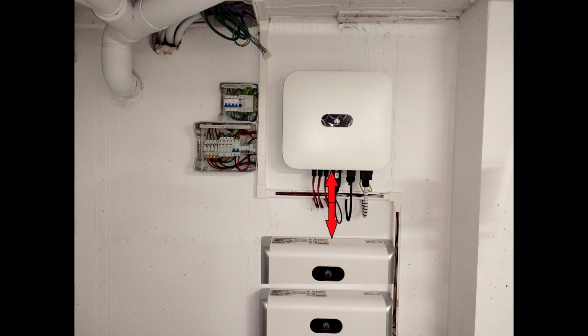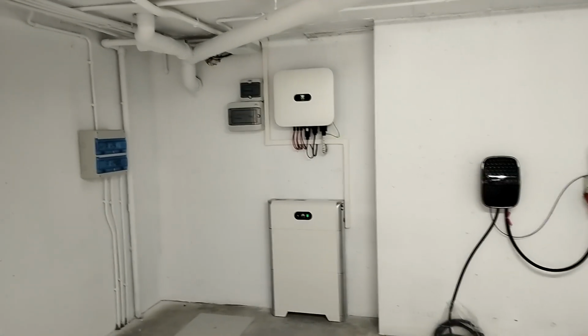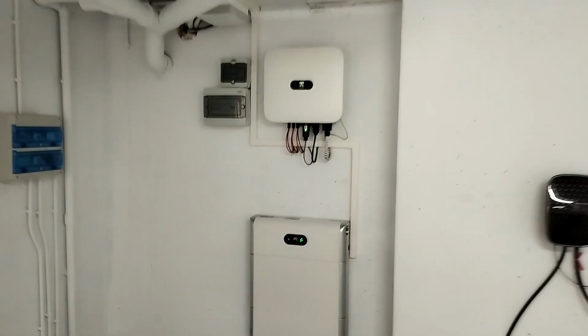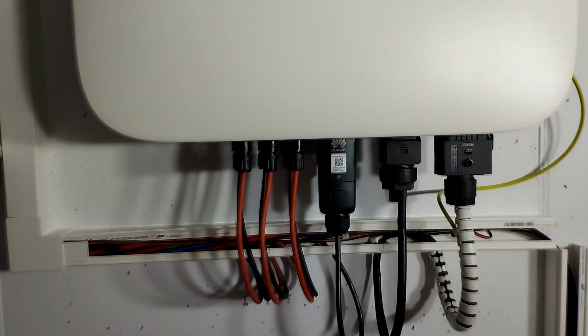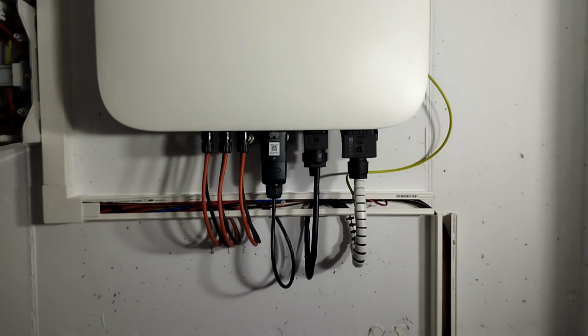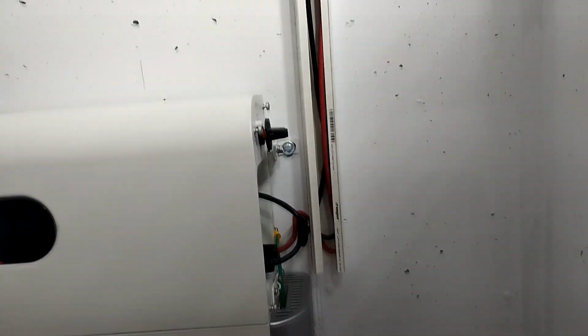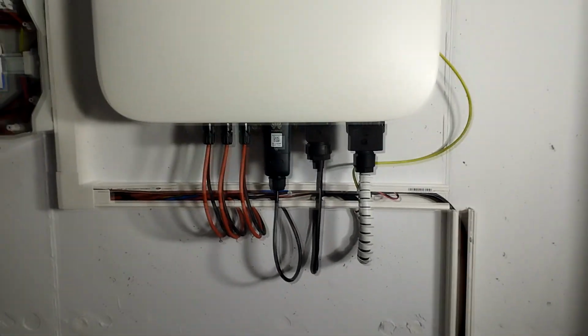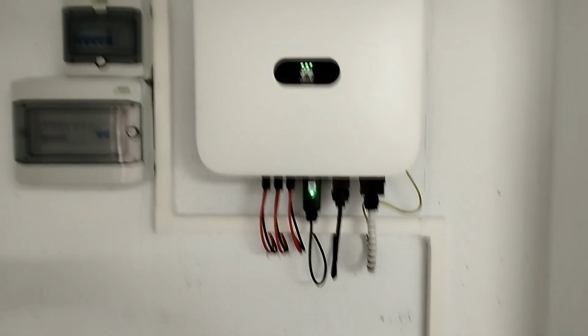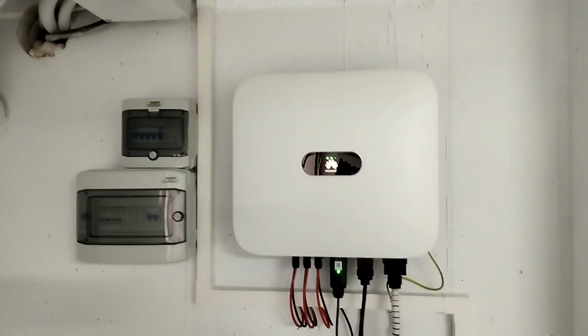Naturally, both the inverter and the battery are heavy, especially the battery, and must be securely mounted to the wall. All electrical and communication cables are connected using appropriate connectors and cable glands to ensure proper sealing. Regarding cables and protective devices, we use only certified, high-quality materials. Cutting corners here is never acceptable. Cables are installed inside appropriate conduits, both flexible and rigid, as well as trunking.